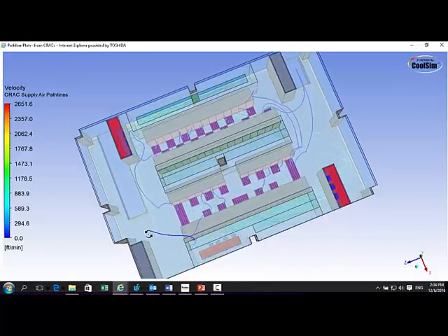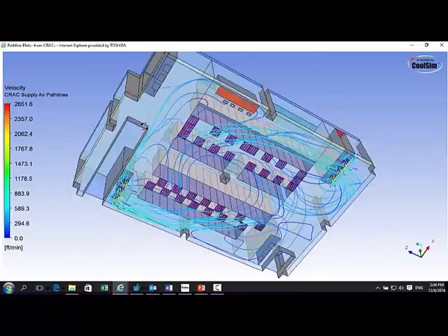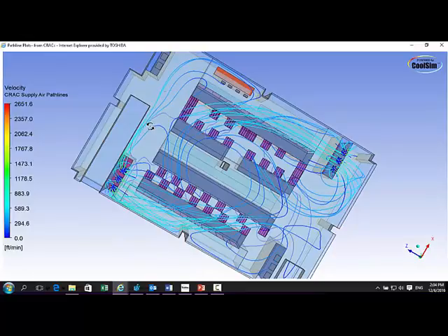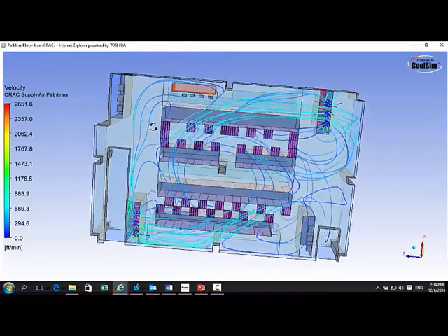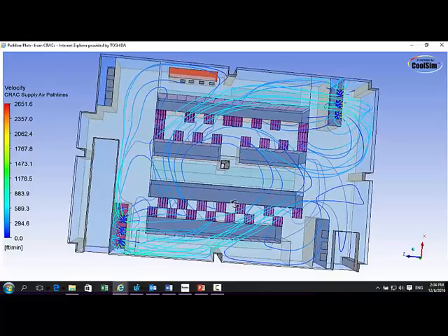The operators seemed to think that was a good way to even the load on those units. But in fact, it does not work that well, because the airflow under the room gets a little swirled in the center. It creates a low pressure. You can see it right here.